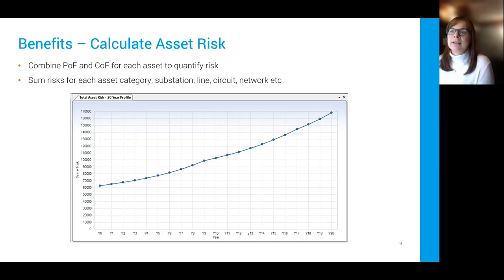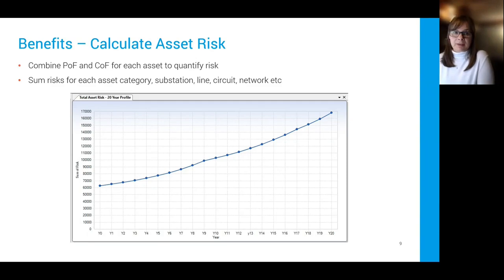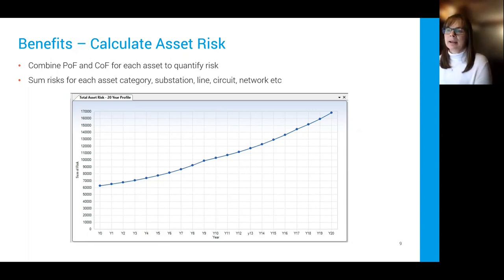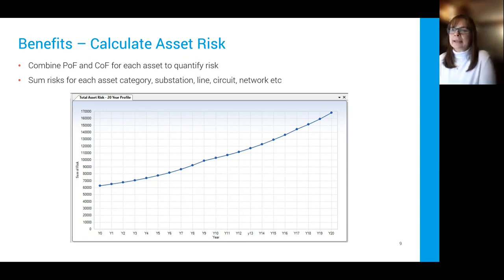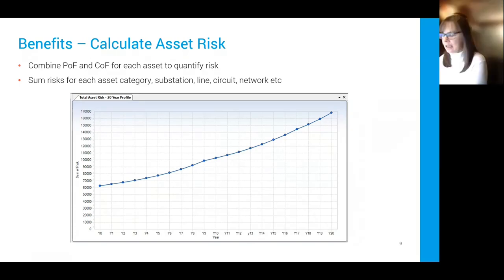To represent assets as risk, we combine the probability of failure (PoF) with the consequences of failure (CoF) for every asset. Consequences of failure in common methodology are expressed in money, so having a monetized value is really useful — you can then create a risk value in dollars, pounds, or whatever currency you use, and sum up that risk for a fleet of assets, a network, a line, a substation, or a circuit.